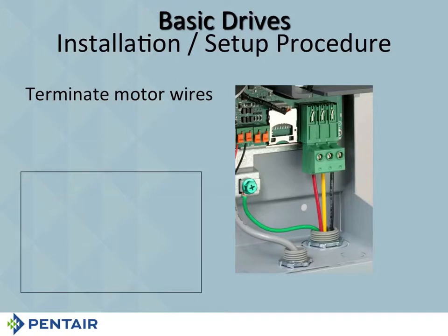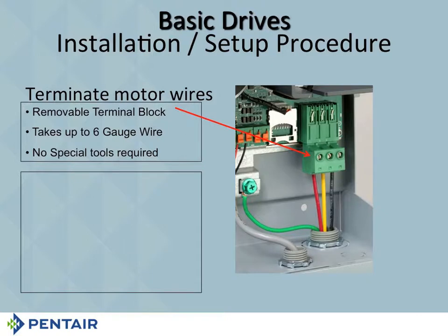You always want to hook up the output first. Safety factor, okay? Always hook up your output first. So when you're hooking up your output first, right there is your removable terminal block. It will hold up to number 6 gauge wire. Now remember, number 6 gauge wire is really kind of hard to move around, so you may want to leave it in there for 6 gauge wire. But for some of the smaller stuff, you can take it out, okay? No special tools. You just have to have a standard screwdriver small enough to fit in that hole where the screw is, okay?